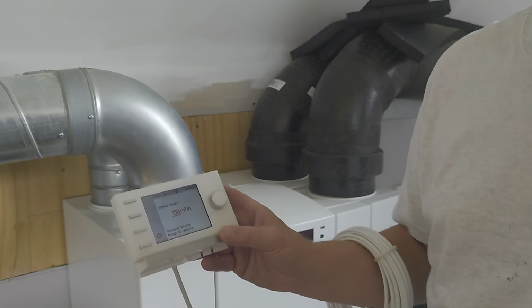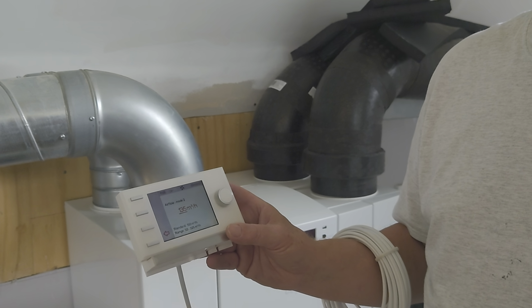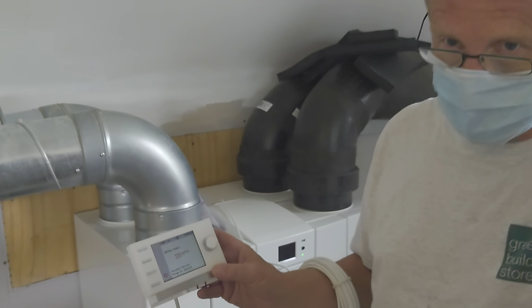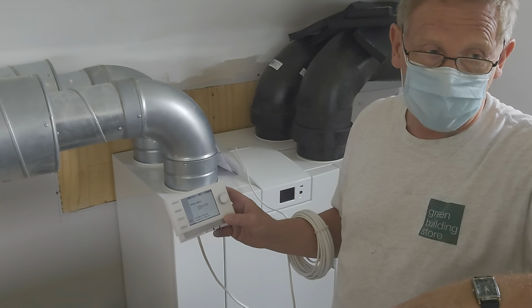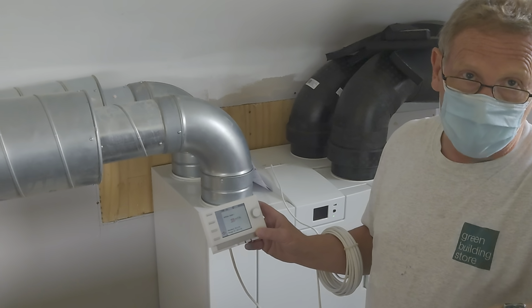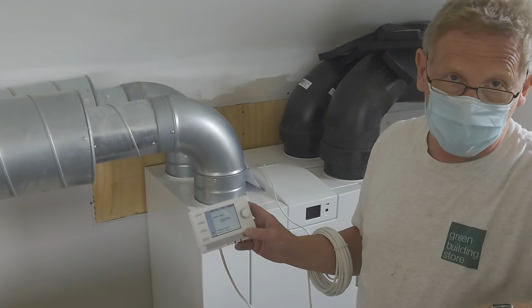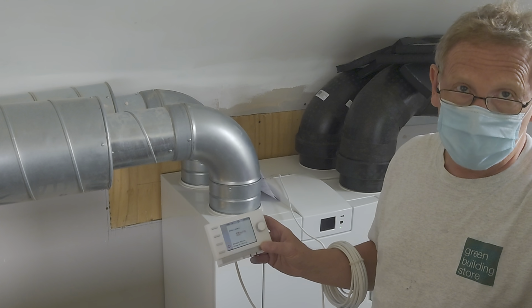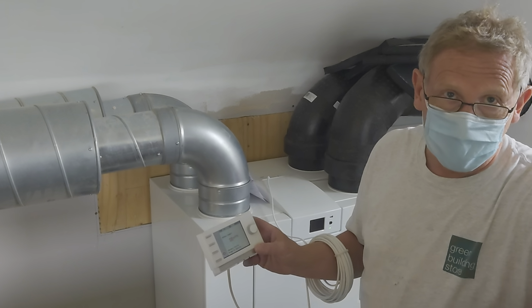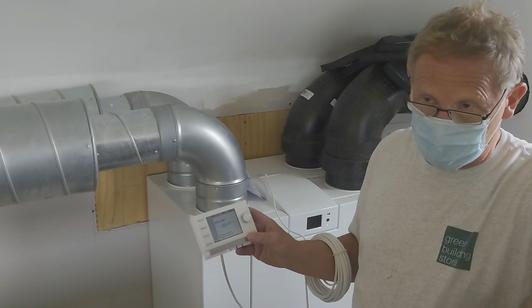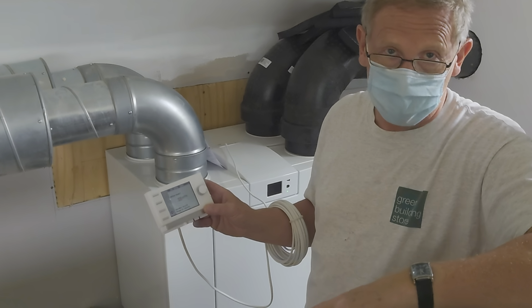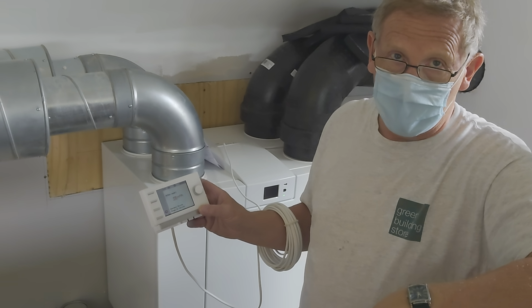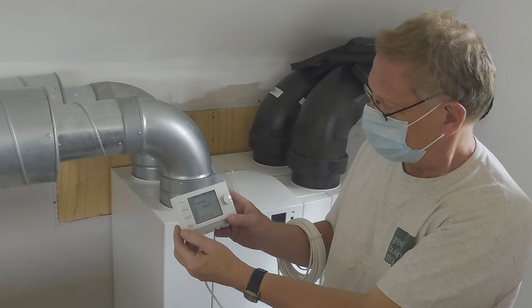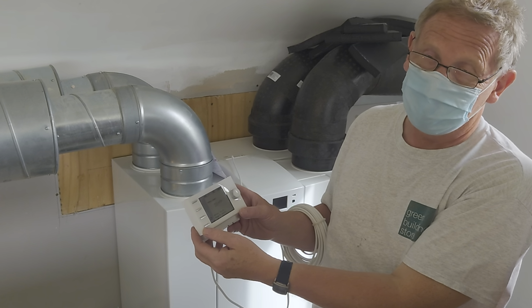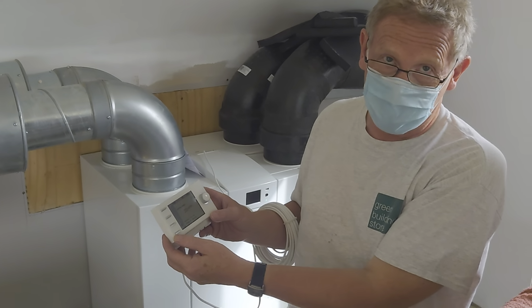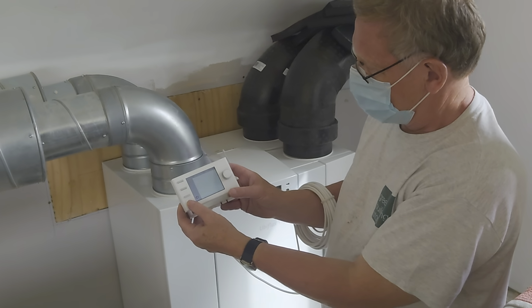Flat out, no. It'd be very noisy. Also, the fans in the machine need some headroom to speed up when the filters start to clog up, because the fans will try to maintain that airflow regardless of the filters. So as the filters start to clog up, the fans will speed up. And does it give you a warning when the filters need changing? Yeah. But it's not based on the state of the filter, it's based on time. Okay, so you can still make a decision whether you want to.